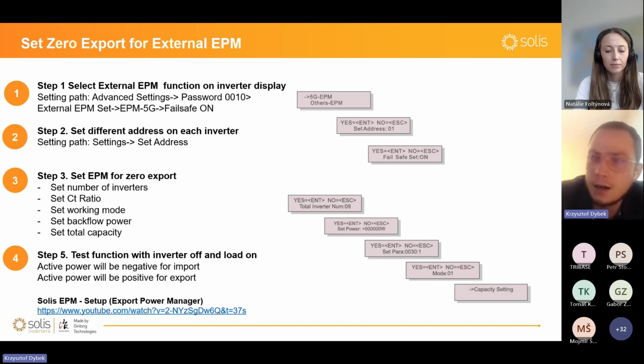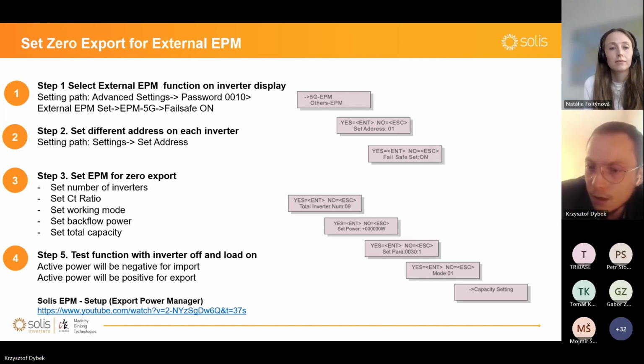Yeah, and the last step is just to test the function with the inverter off and the load on. So active power will be negative for import and active power will be positive for export. So the best way to test if the meter and CTs are correctly installed is to just disable the inverters and then check on the meters or the EPM screen if your real power is negative on all phases. If any of your phases is positive, it means that your CT is reversed.